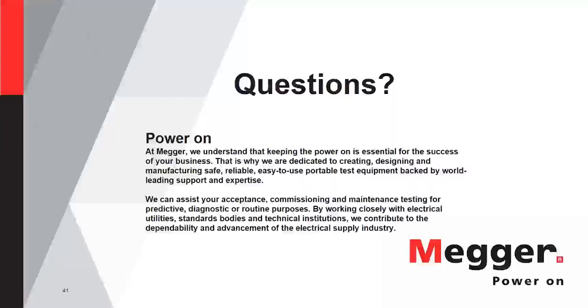Otherwise, if you don't do that test, you would have to make the argument that if you do a capacity test, the batteries obviously have to have continuity, or they're going to fail that capacity test. You can also take the argument that if you're doing a full ohmic test, and there's an open somewhere in the string, you're going to find it. But again, the direct measurement is to inject the current directly through the entire string, which is very simple with the BITE2. It's actually part of the test.